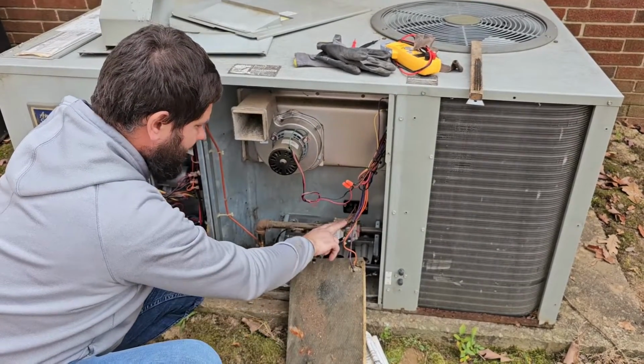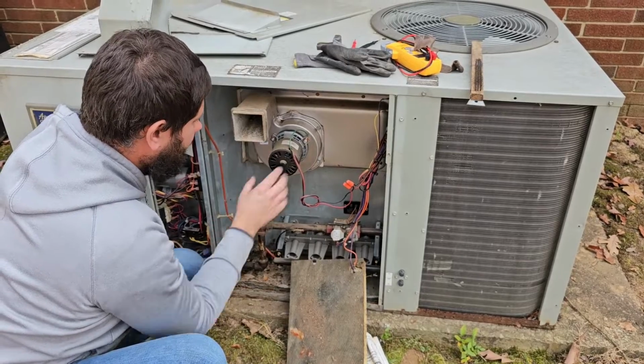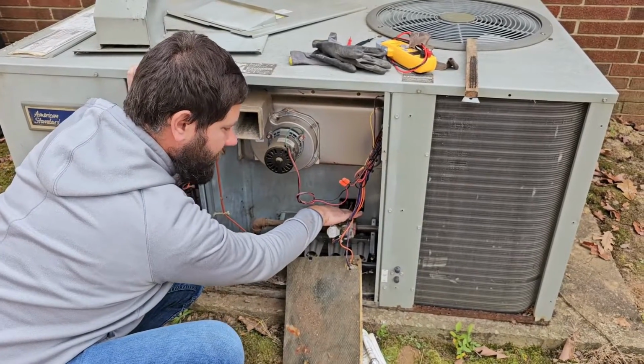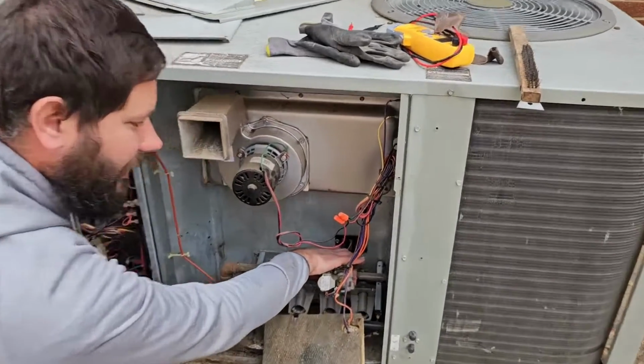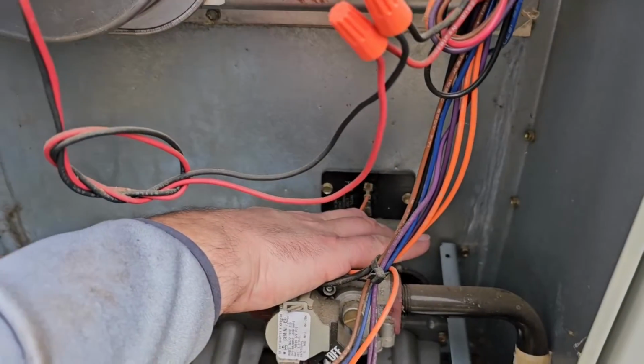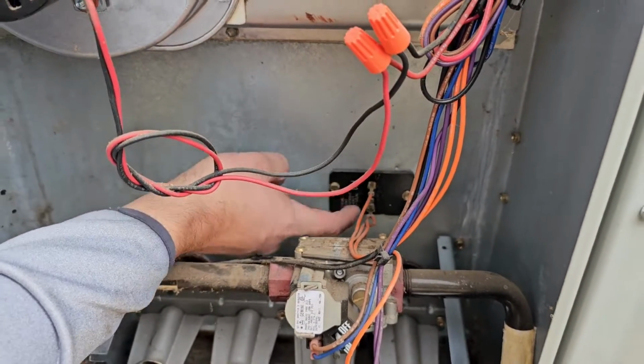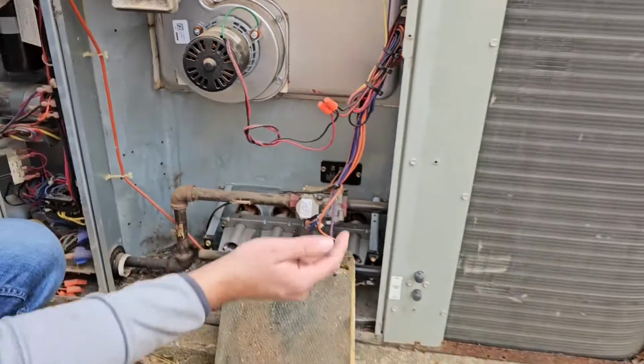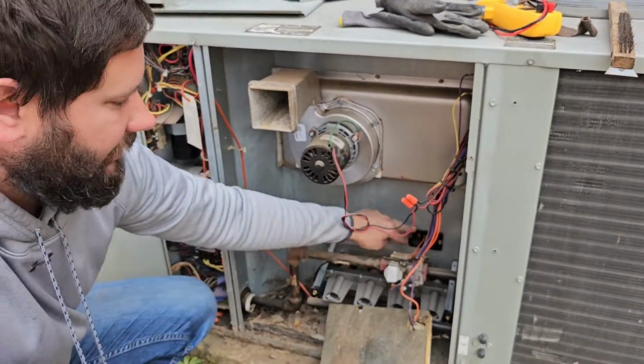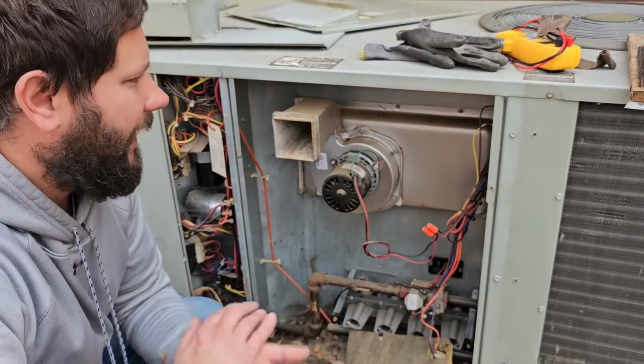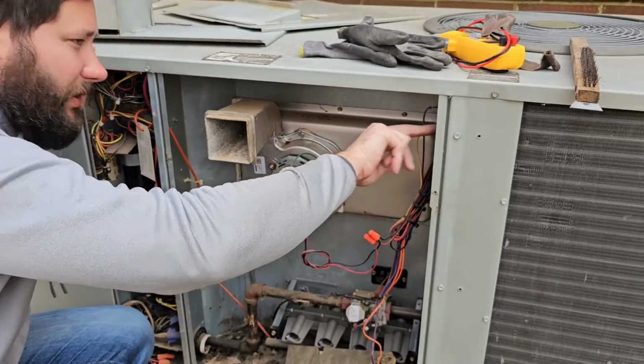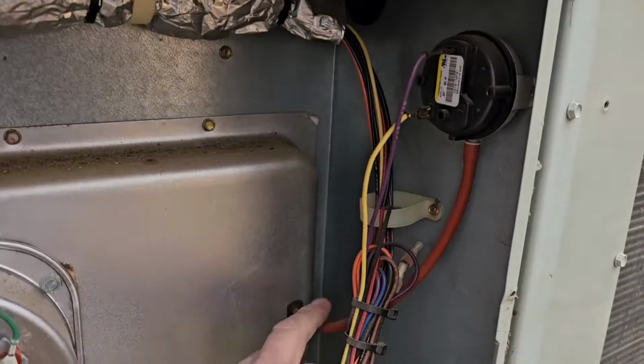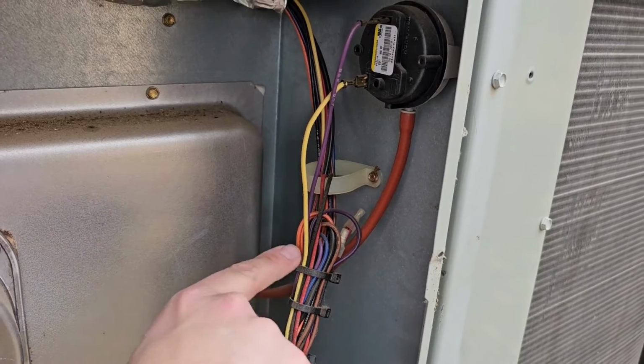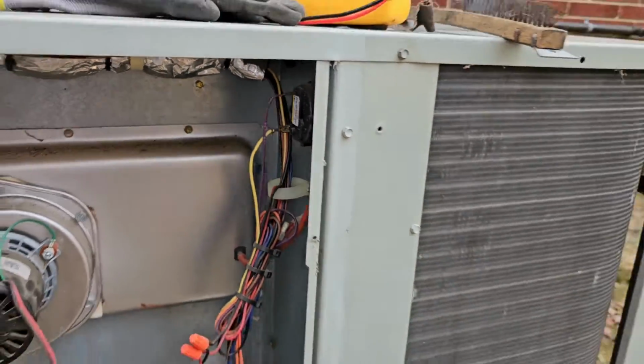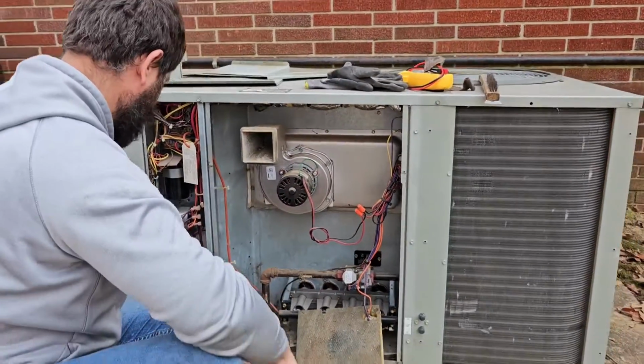We got our gas valve here, and we got our inducer motor. This is a limit switch right here. See this? It opens at 190, and this is a part that we keep in stock. Be careful when you tighten the two screws, because it's plastic, it'll crack. It's pretty easy to crack. This right here is the pressure switch. Whenever our inducer motor starts and pulls a vacuum, that negative pressure closes that switch.